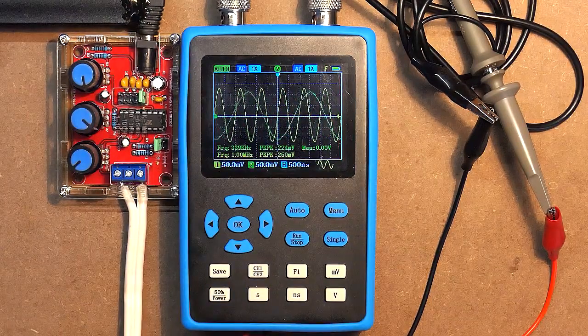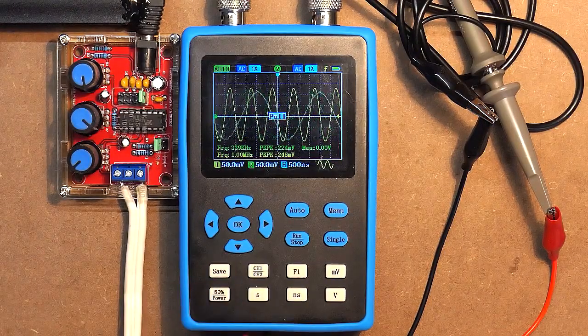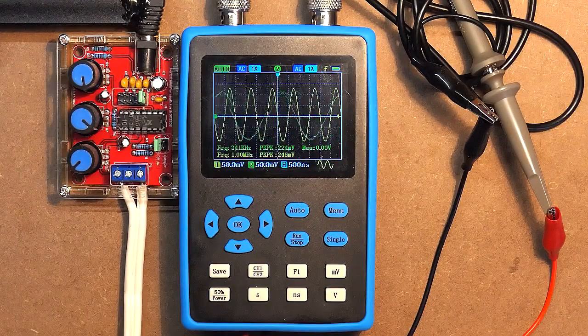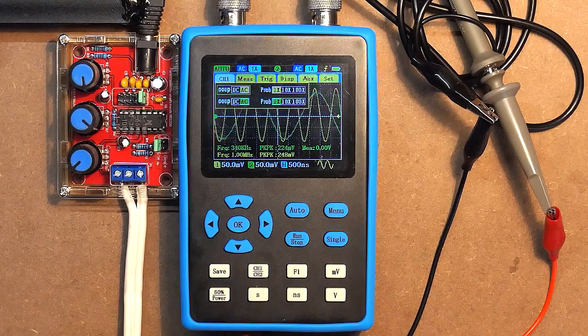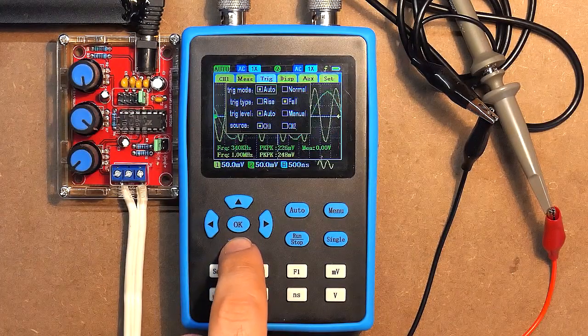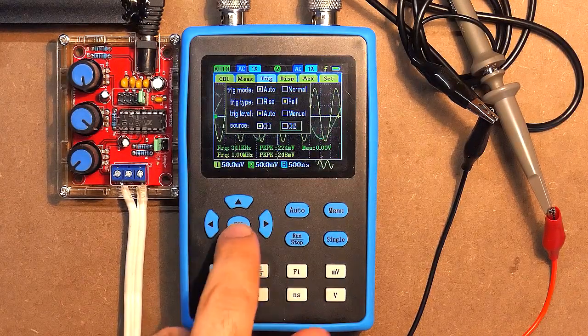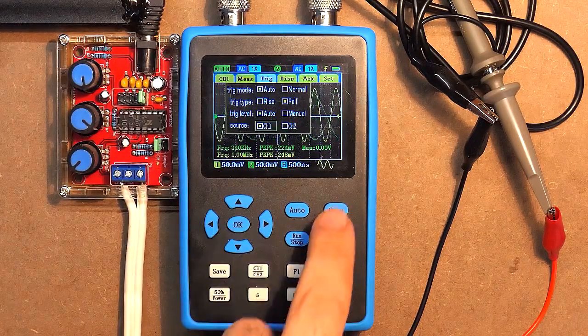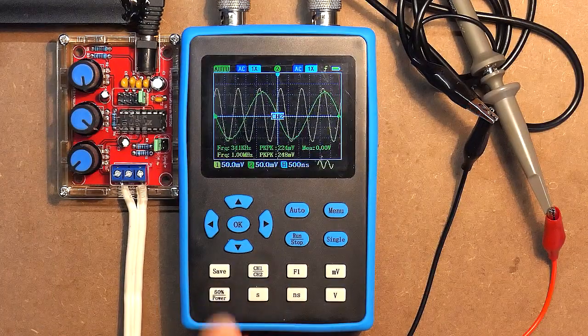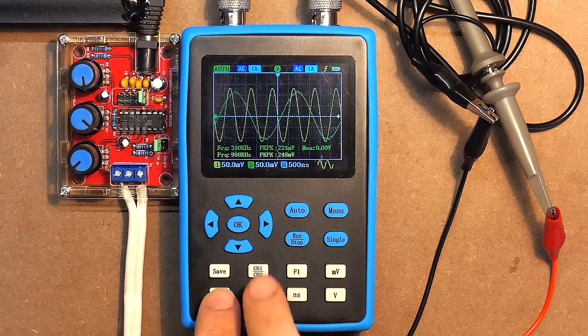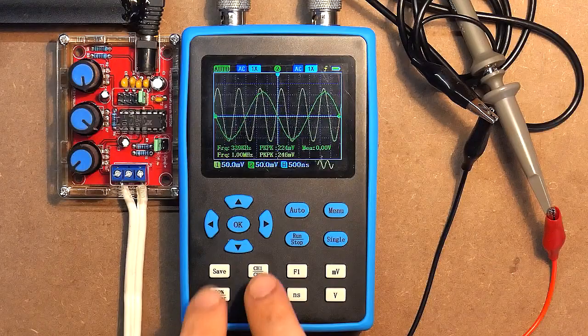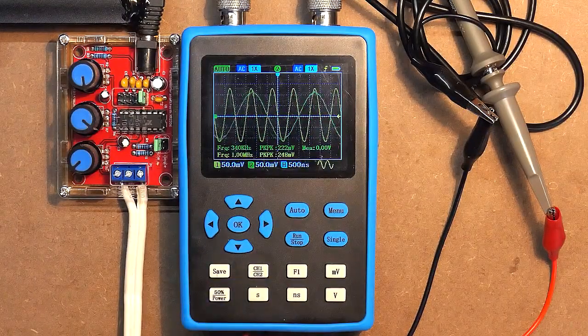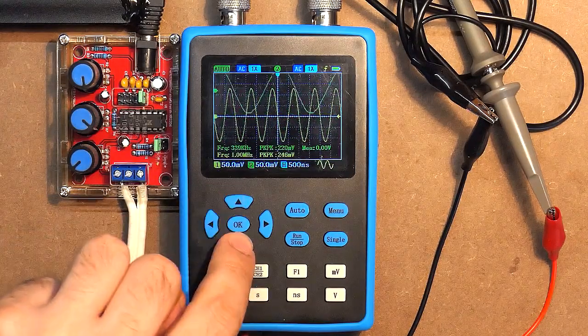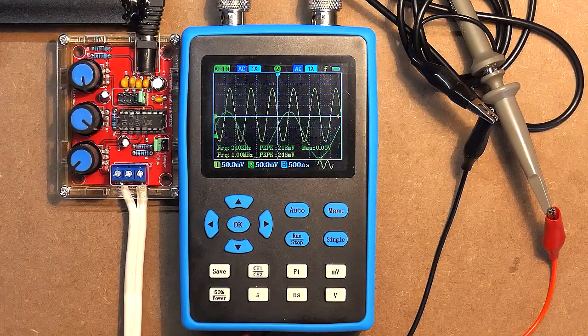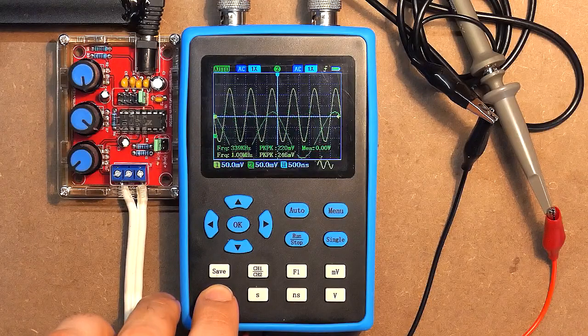Trigger rising or falling edge, power save, fall, rise. In order to switch the trigger source, also there is no need to go to the menu. We simply press power and channel 1, channel 2. Here the arrow is green and now it's yellow. In case we use up and down arrows, we move the priority channel graph. But if you would like also to move this low priority channel graph, power.